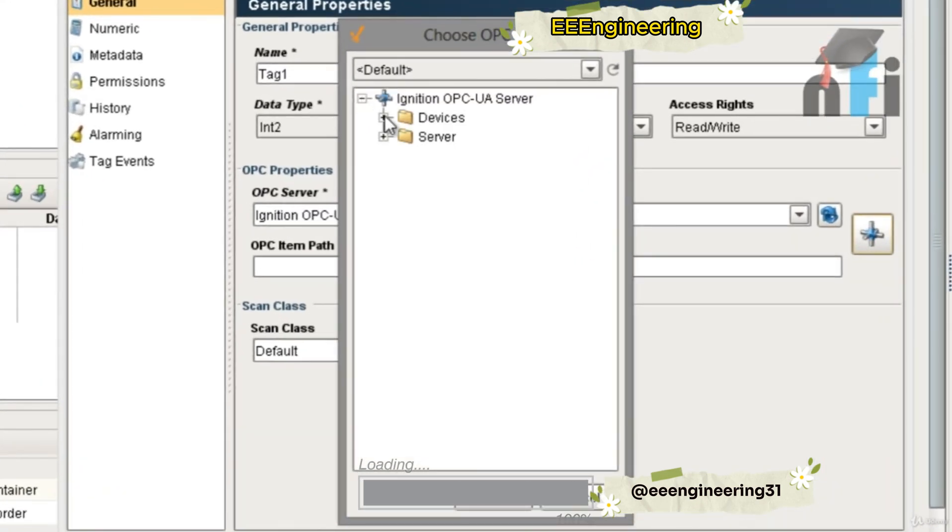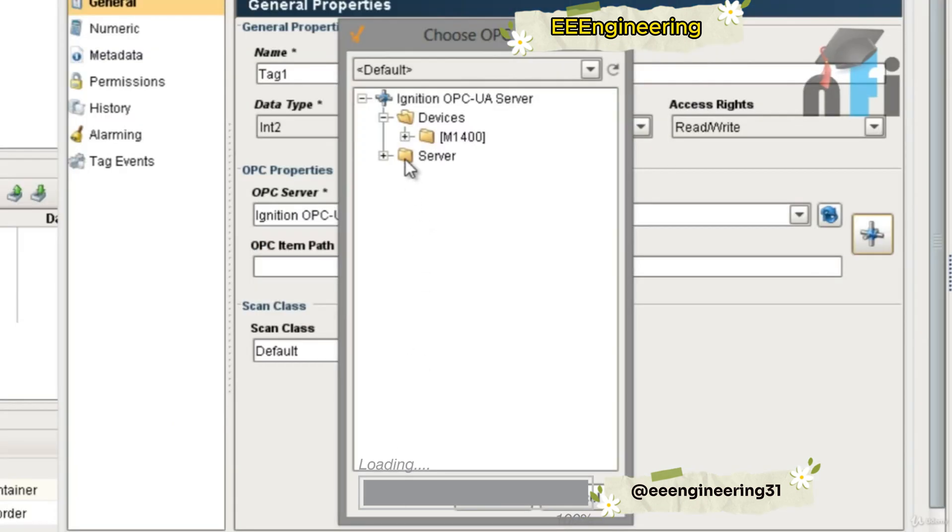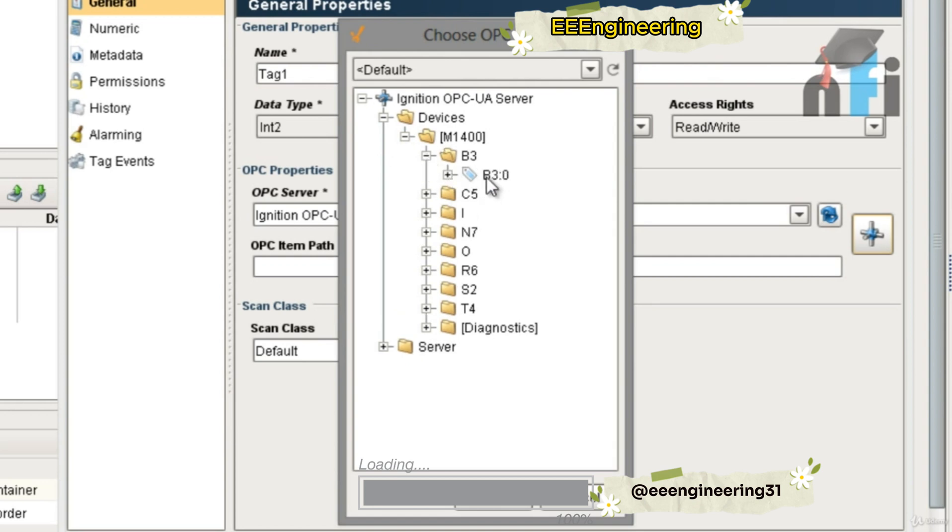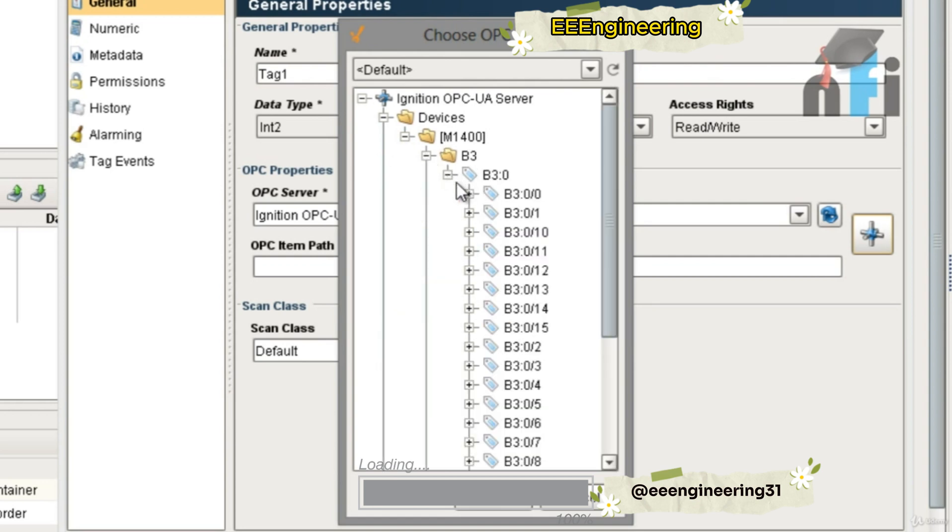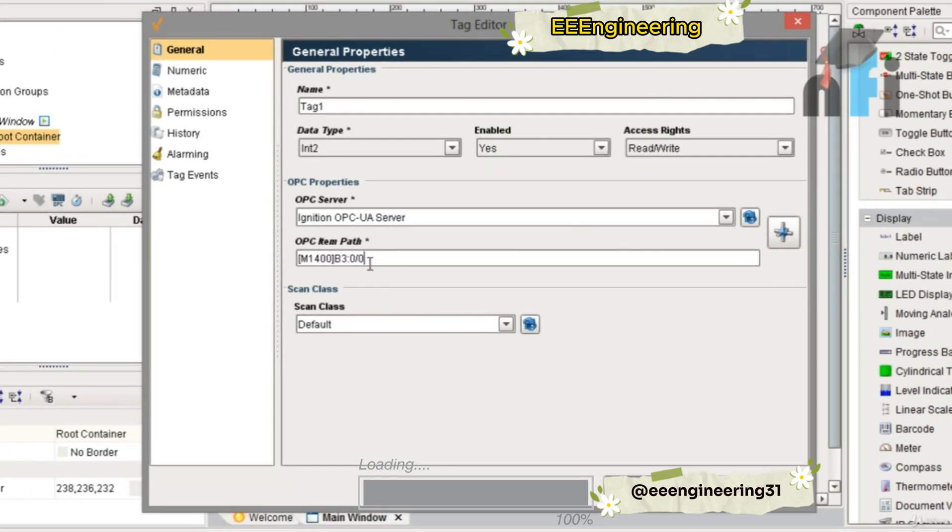Expand your server, expand your devices. This M1400 is similar to what we saw here. Click on M1400 and you'll find different addresses. We are using B3, this is the word address, and B3:0/0 is the one. Click OK, you'll find the item path given as B3:0/0, and before that in brackets you have your device name. Click apply and OK, so you have tag1 which is linked with B3:0/0.